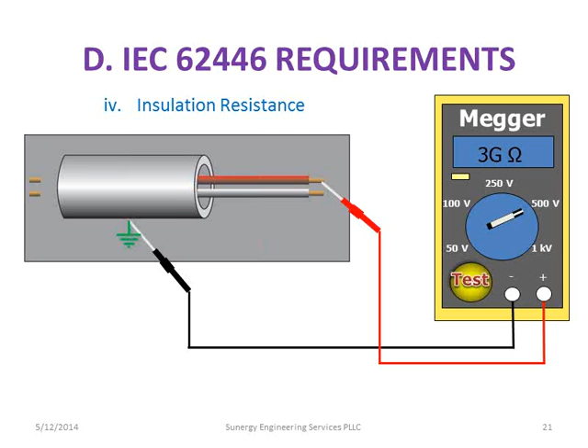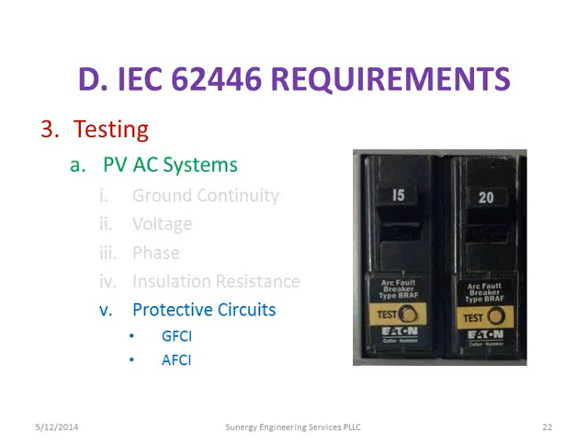I've done a couple jobs where the utility has required the main feeders to be megged, going back to the panel, which was kind of unusual. And then you have to check your protective circuits, whatever they are. If you have a GFI, you have to show that it was working properly. Now we're starting to see more arc fault required, so arc fault also has a testing circuit, so you can verify that it actually works.